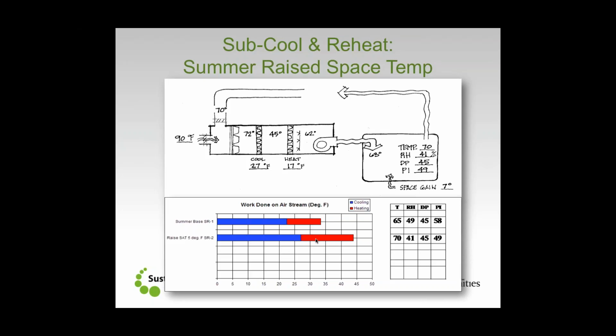Because the only thing we did was change the set point in the space. We didn't change what the cooling coil is doing. The cooling coil still thinks we have to dehumidify to a 45-degree dew point. That's what it's told to do. I do this all the time. And if I'm creating a 45-degree condition leaving that cooling coil, well, now I've got warmer air at 70 degrees blended with the 90 degrees coming in. So guess what? I just used more cooling energy in order to achieve my dew point.